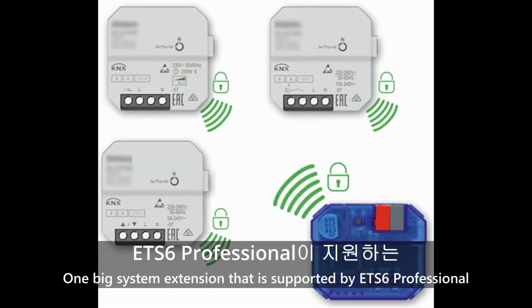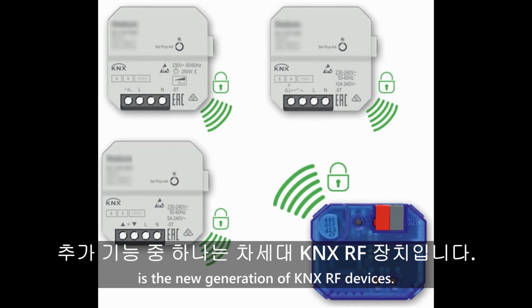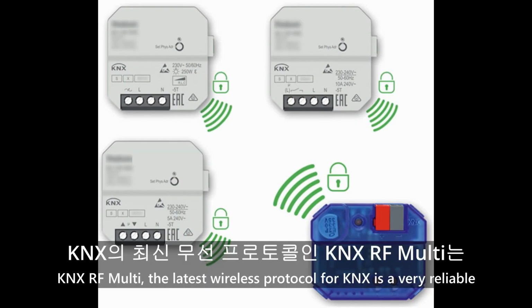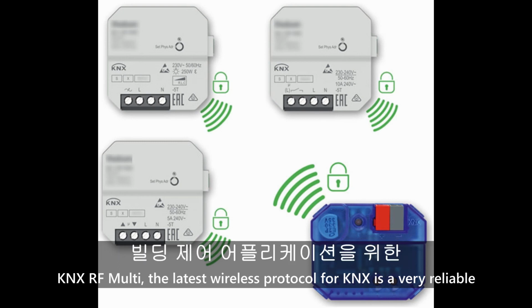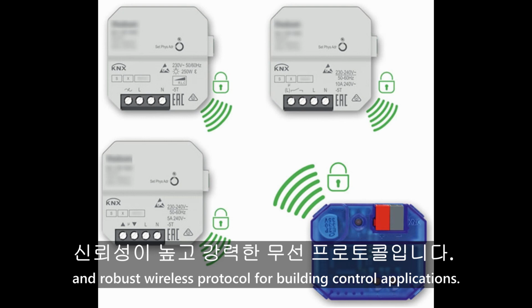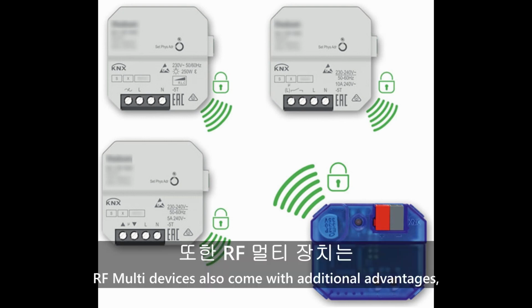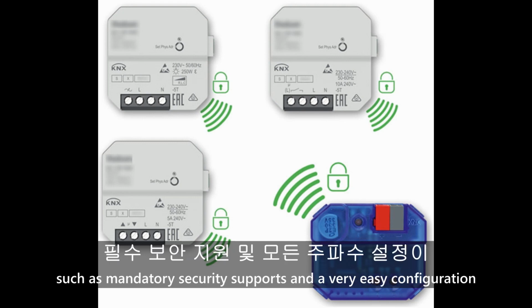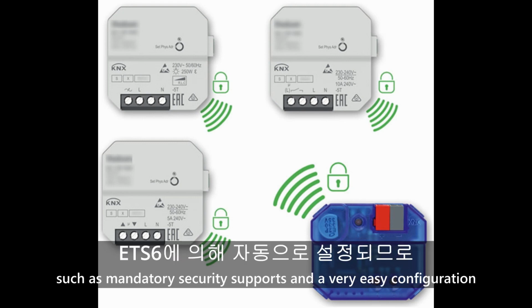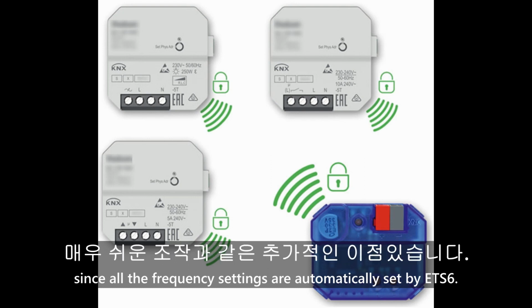One big system extension that is supported by ETS6 Professional is the new generation of KNX RF devices. KNX RF Multi, the latest wireless protocol for KNX, is a very reliable and robust wireless protocol for building control applications. RF Multi devices also come with additional advantages, such as mandatory security support and very easy configuration, since all the frequency settings are automatically set by ETS6.